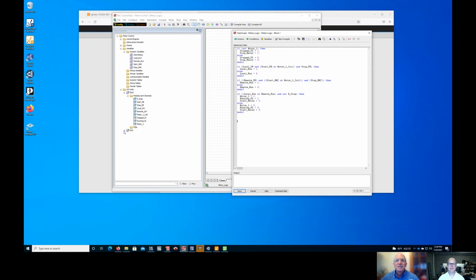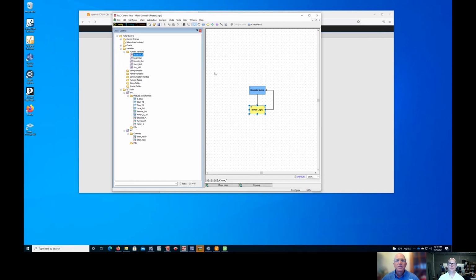So there are two different devices I'm hooked up to. There's a Rio that I'm using as well, so there are a couple of relays built into it, and I'm actually controlling both. It's nice to have remote I/O, because if you run out of space on your PLC cards, you can just pick up a nice little remote I/O device, and that fits well into this overall architecture. So that's all I'm doing, solving all those logic statements. It's literally how you build your ladder logic, writing all this stuff out. So it's pretty slick to work with that way.